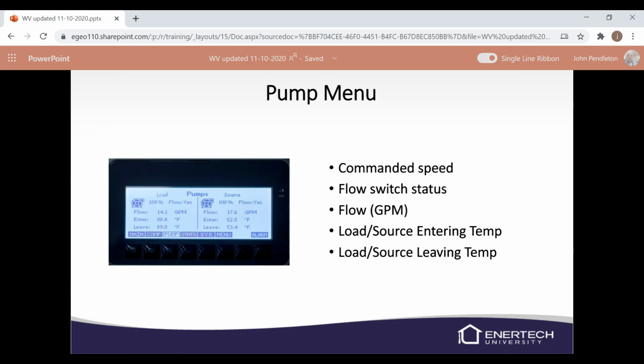Pump menu, here it will show you both pumps, what the entering and leaving water temperatures are, the GPM, whether your flow switch is open or closed, and the percentage that the pump is running. It'll also show the volute again spinning.